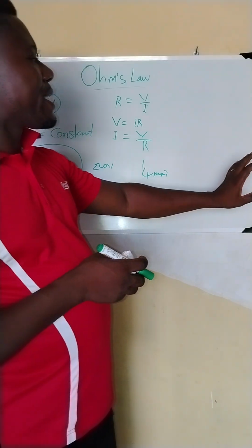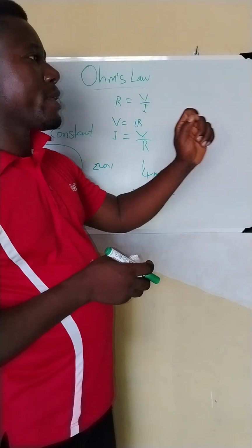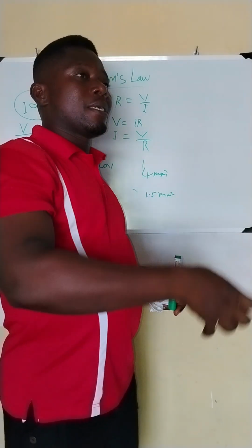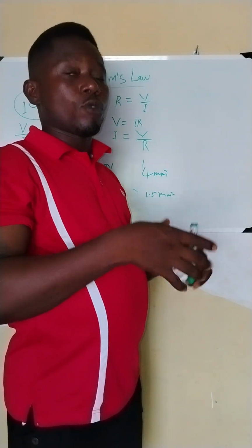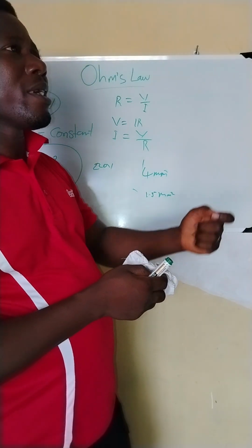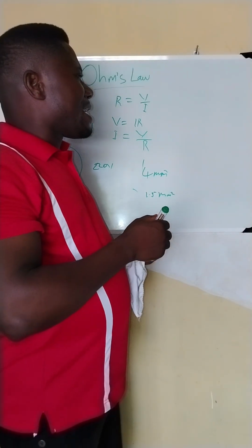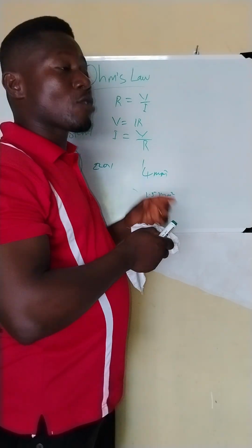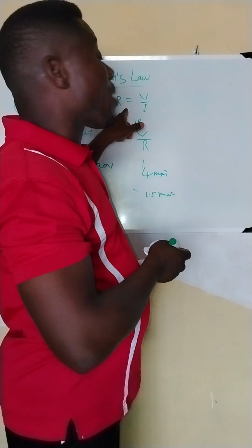Now, if you go closer to the cable, if you can have access to the cable, I'm not talking of you touching the live wire, I'm talking of the insulation material, the rubber with which the cable is coated. You notice that if you touch the cable, as time goes on, it will be heated up. The reason is that the cable is not the size of cable that's supposed to carry that amount of current. With time, you notice that the current flowing will not be the same current that was flowing before, because at this point, the temperature is increasing.